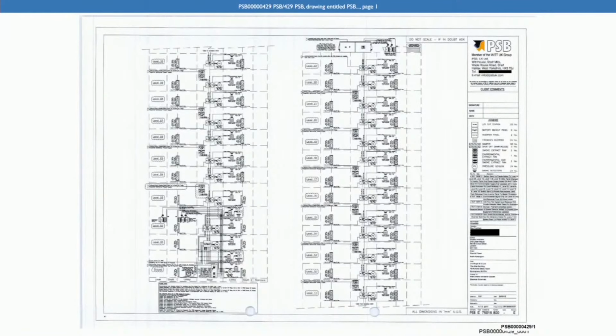Now, we don't need to read the detail of this drawing, but can you just explain in general terms what was the purpose of this document, this electrical schematic? That electrical schematic lists all the items that are connected to the control system on each level, what the items are, what they do as such, and I would use that effectively as a tick sheet. So depending what level I was working on, I would work out from the outstation and look at every item that was connected on that outstation. So the north and south shaft dampers, the pressure detector, the fireman's override, etc.